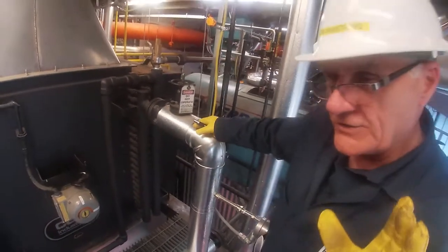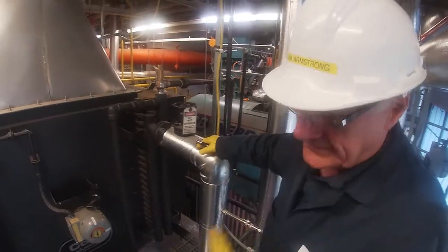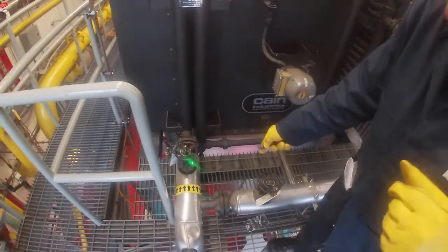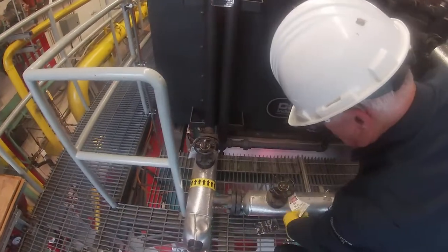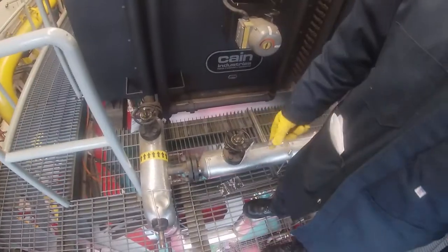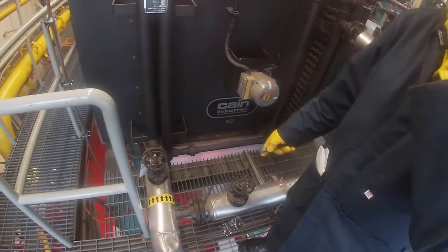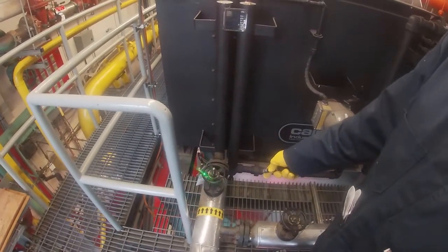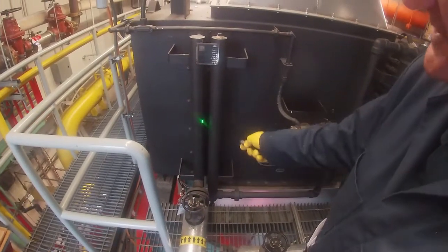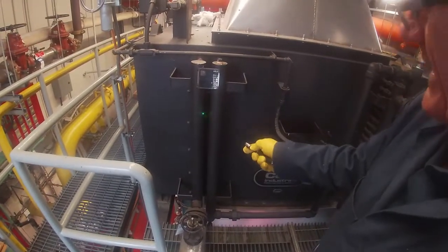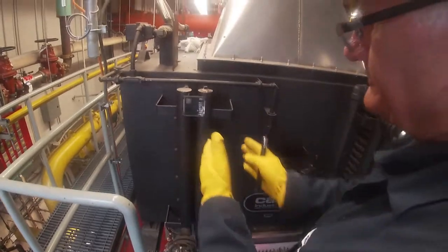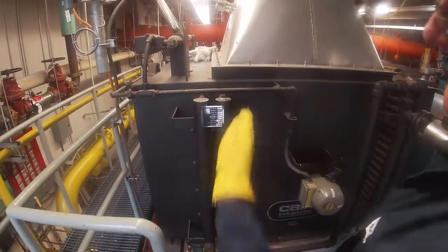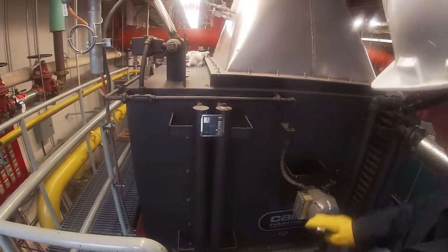If, on the other hand, you want to go through the economizer, which we always do, you'll take the water through here. This valve's going to stay closed. You'll see that we've got a do not operate tag on it, so somebody doesn't accidentally open it. We've got do not close tags on this so that they don't mess it up. The water comes into a header here, and on this header, there's tubes going all the way along the side. And those tubes are where the gases will go.